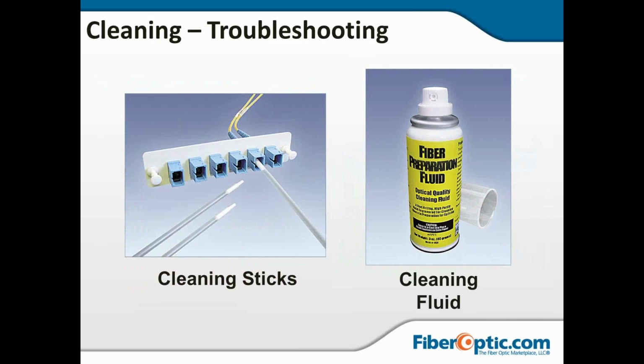All right, cleaning sticks. I have mentioned those when we were looking at the earlier picture. If I've got to do wet cleaning, I will moisten one of these and I will use it for cleaning. I will immediately go in with a dry one and do my best to dry up any residual cleaning solution. As I've mentioned a couple of times, anything wet left inside the bulkhead is going to attract dust. It's going to attract dust more readily than a dry connector. So you want to make sure and dry up any of your cleaning solutions. Also, when these cleaning solutions air dry, they will leave a residue. Both of these are bad ideas.